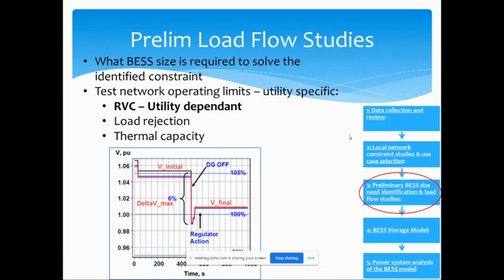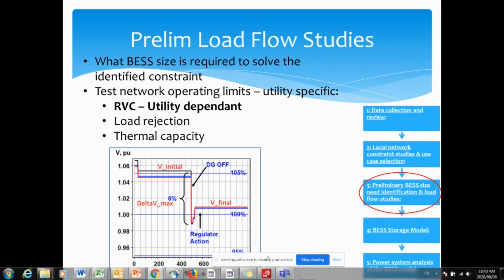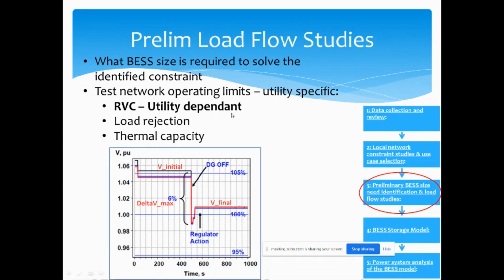One of those operating limits is what we call RVC, rapid voltage change. Different people call it different names, I've seen SVC, step voltage change, and a few other terms used to define the same thing. This is utility dependent, some use 5%, some 6%, and I've seen some allowing as high as 10% on an RVC.